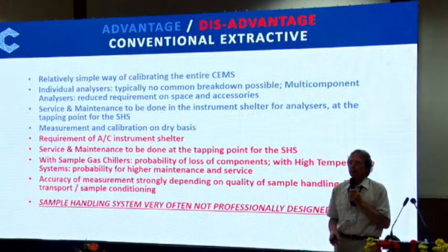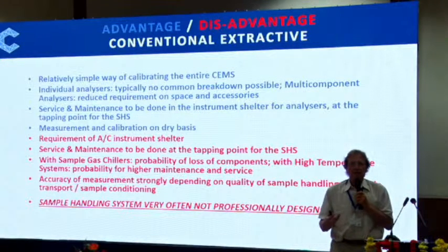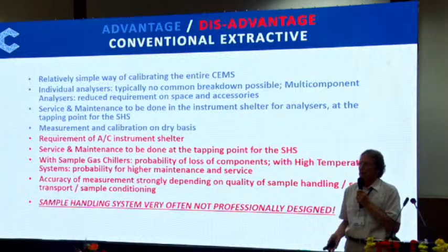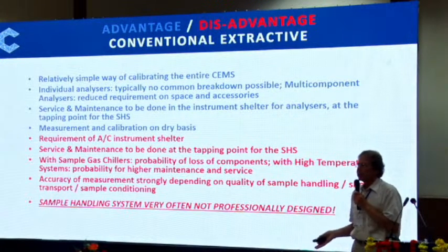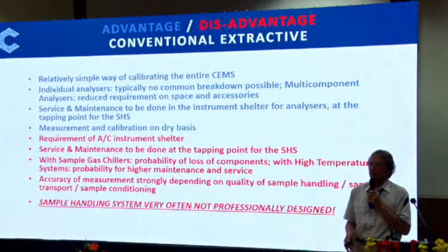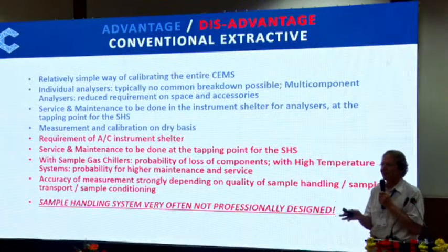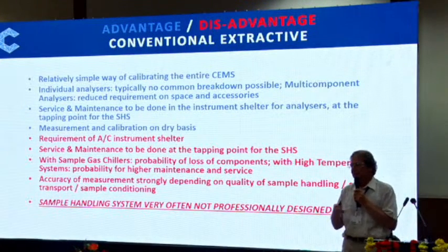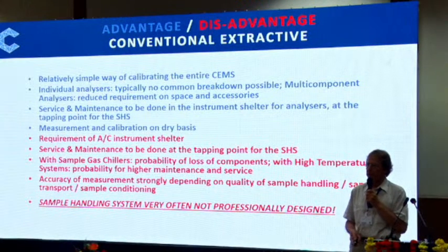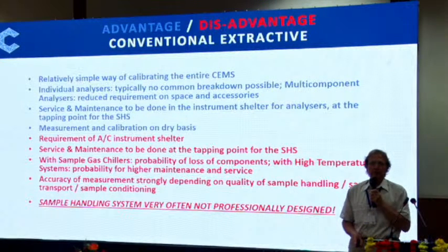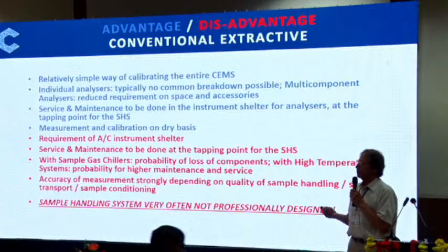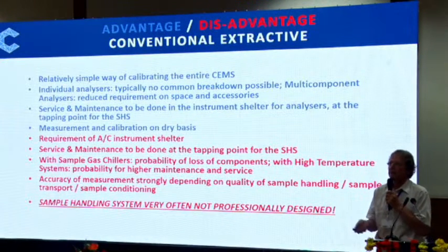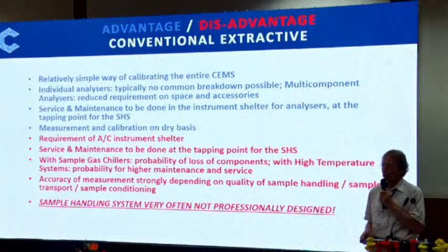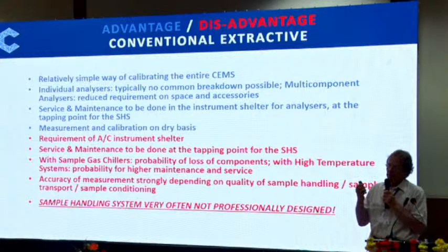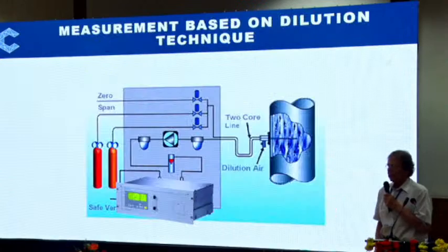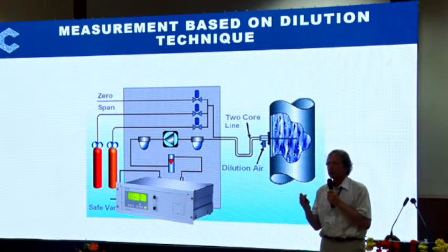In sample gas chillers, I'm losing components. Yes, that is the case. SO2 is water soluble, NO2 is water soluble. No way to do an ammonia analysis or HCl analysis or HF analysis with a sample gas cooler. Now you're producing very good zero gas, and everything is in the effluent. But these have to be hot temperature or dilution-based instrumentation. And it depends on the design of the heat exchangers how much of the sample gas components are diluted or soluble. And again, the sample handling system should be very well designed to match the application.